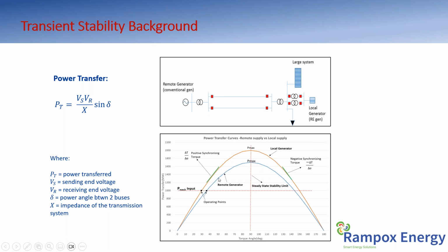Looking at indicators of stability, what we call positive synchronizing torque, you'll see that it is better with the local generator than the far-off generator. With the far-off generator, the blue part, your operating angle is bigger. To transfer the same amount of power, you have to operate at a higher angle. If you're closer, you can reduce the operating angle on the rotor of the machine, the rotor angle.